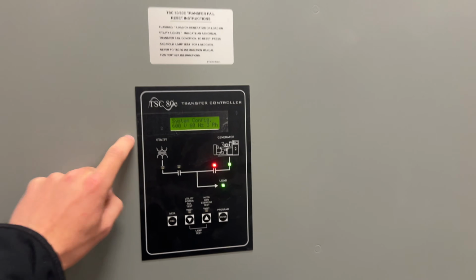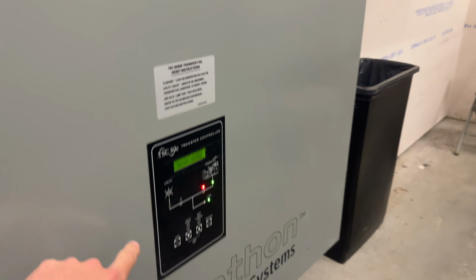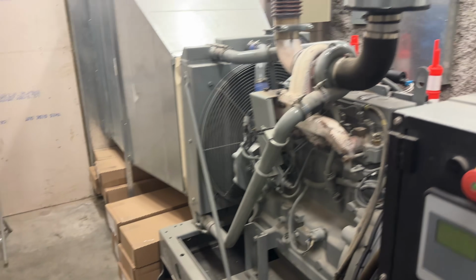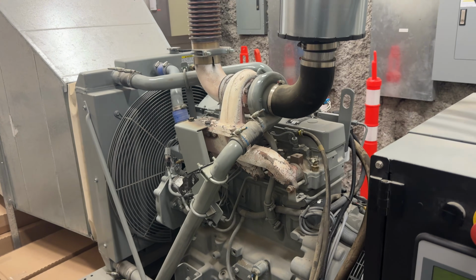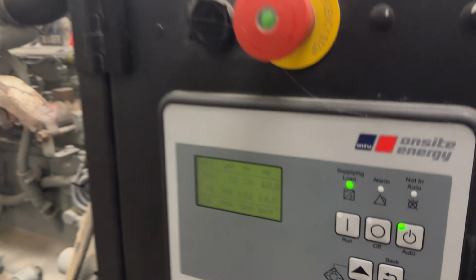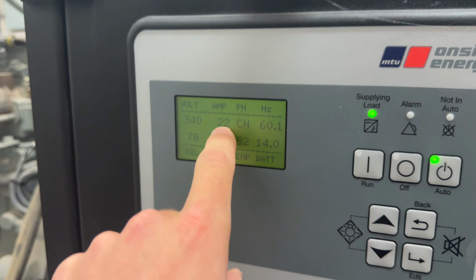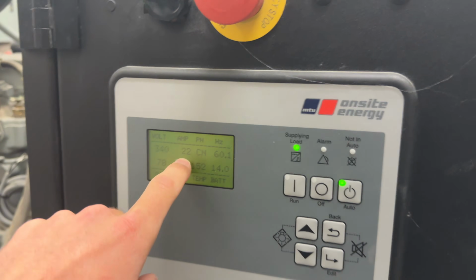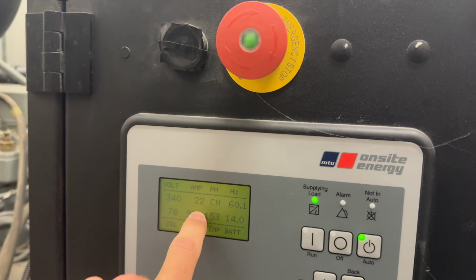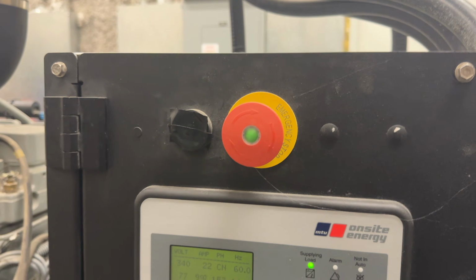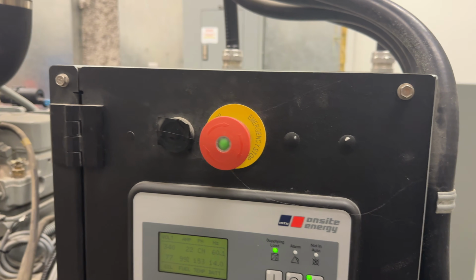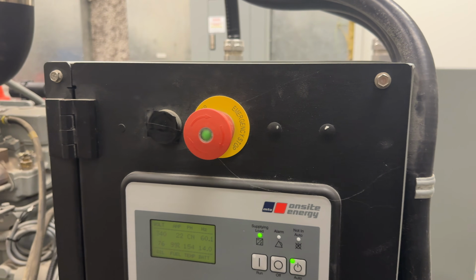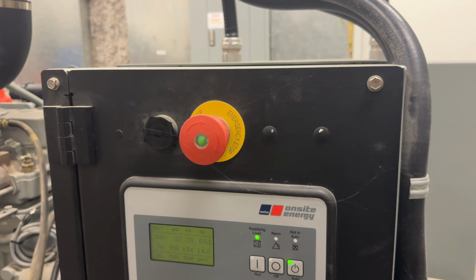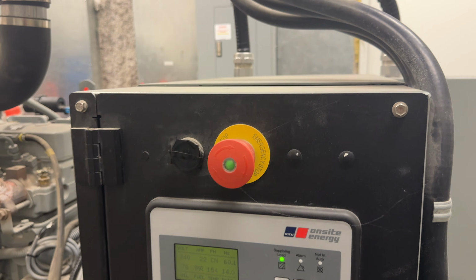This is our backup power. This is our life safety transfer switch. If we look right here, we're pulling 22 amps. Remember, we can pull up to 72, so we're not loaded too high. That's because we're only running all the emergency lighting. The biggest load here that's on generator is the smoke control system. That's a huge, massive motor load.